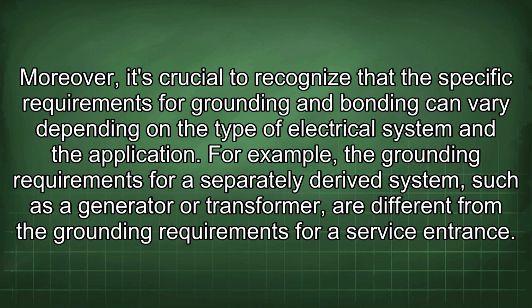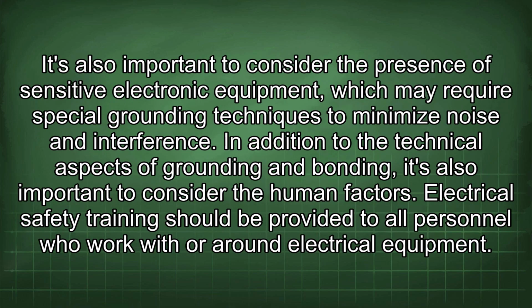Moreover, it's crucial to recognize that the specific requirements for grounding and bonding can vary depending on the type of electrical system and the application. For example, the grounding requirements for a separately derived system, such as a generator or transformer, are different from the grounding requirements for a service entrance. It's also important to consider the presence of sensitive electronic equipment, which may require special grounding techniques to minimize noise and interference. In addition to the technical aspects of grounding and bonding, it's also important to consider the human factors.